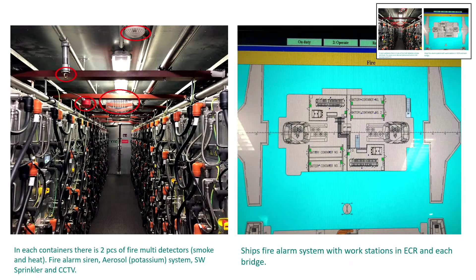Inside the containers, we have, of course, fire multi-detectors, smoke and heat, fire alarm, sirens. We have an aerosol system that can extinguish a fire inside the container if we have a short in the power cables or something else. But of course, it cannot handle a thermal runaway. In case we have a thermal runaway, there's no other option than to release the sprinkler and fill the whole container with water. But then, it's salt water, so you will lose all the batteries in that container. And also, of course, the ship's fire alarm system has detection, and we have it in the ECR and on both bridges, it's a double-ended ferry, so you have workstations on both bridges.